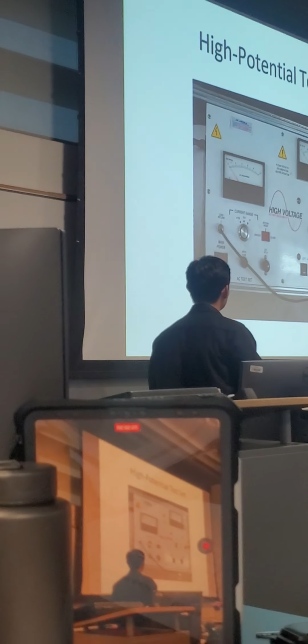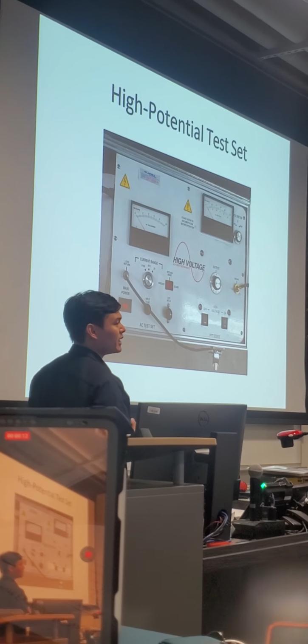A couple other notes. When performing this test, we don't just crank it up; we have to slowly ramp up our voltage while carefully watching our amps. With every increment, the amps might tend to shoot up. In some instances, depending on leakage current, you could be on the lowest scale and it could already top out at 1, meaning you need to change your scale. So what you thought was in the milliamps could actually be tens of milliamps. You have to be able to determine, especially with practice, when is the right moment to change your current multiplier so you're still getting good readings.